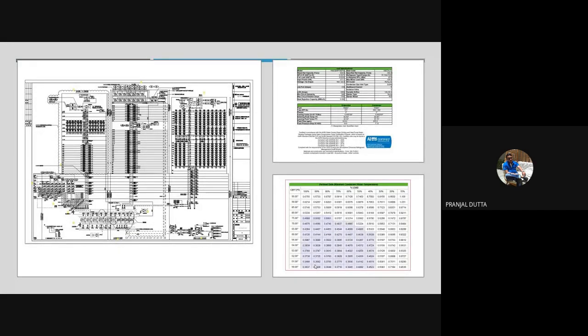So this is the plant layout. This is the chiller's design data. This is the chiller part load data. The part load data means it's different: CEFT means condenser entering fluid temperature, with different condenser entering fluid temperatures at different loading percentages. So kilowatt, this is on COP. Next, kilowatt per ton. Kilowatt per ton changes with the condenser water entering temperature and the different loading percentages. So this data is used to do some calculation for the coefficient. That coefficient needs to be used in the particular application.